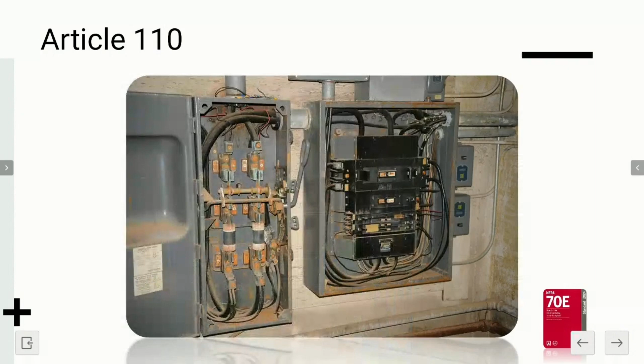Yep. And to that point, as simple as the overcurrent protective devices, the manufacturers instruct you to cycle them, and nobody knows that. They instruct you to cycle them every X amount of days or whatever. Nobody does that, really? Nobody does it. Nobody knows it. What if you walked up and it didn't look properly installed and maintained, and you opened it up and you saw this? You think that if you started switching things off and on, that could cause an arc flash? Guarantee you it will.